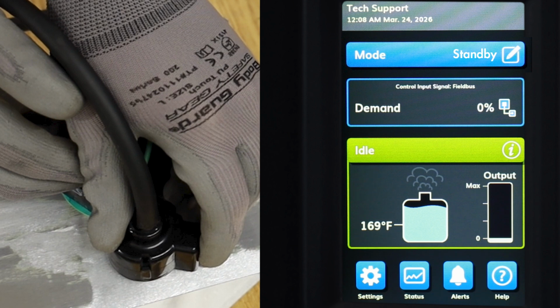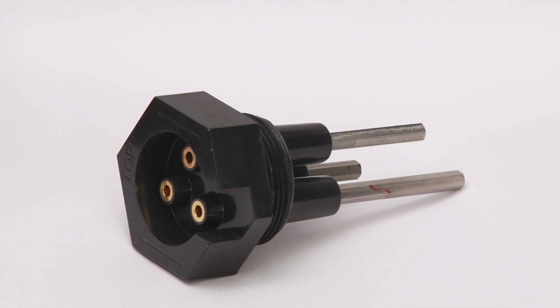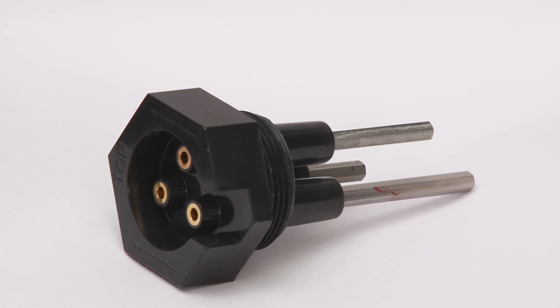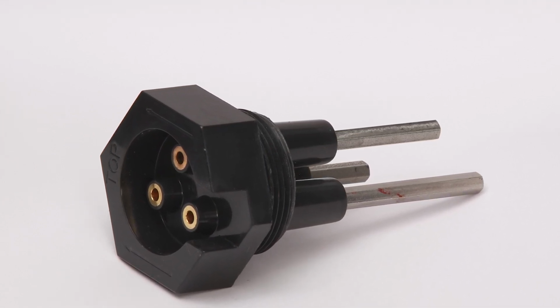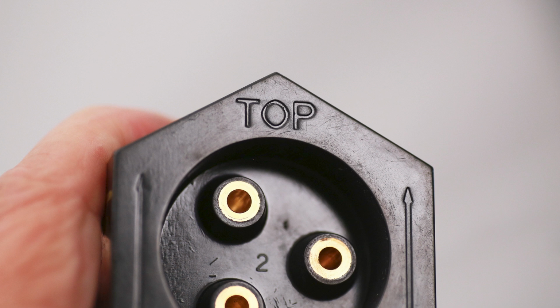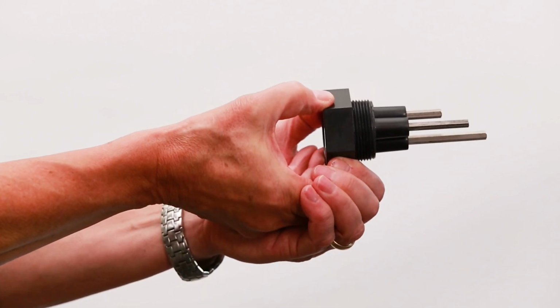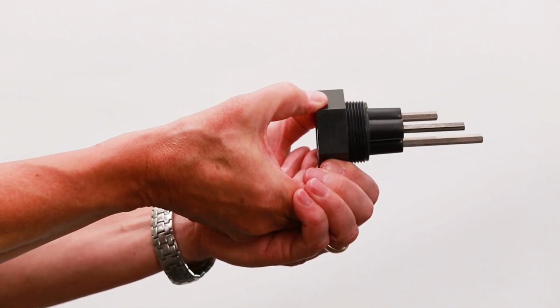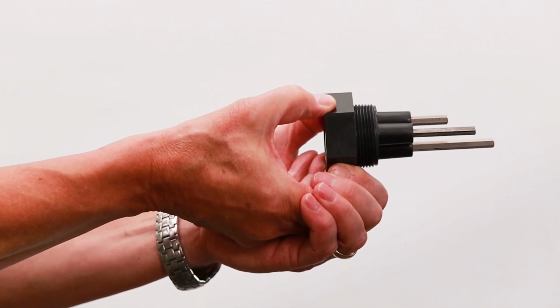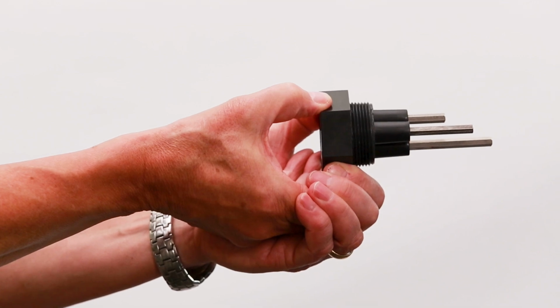It will show full. Another thing to check is that the rods are in the correct order on the probe body. Here's how you check. Orient the probe assembly so the word top is at the 12 o'clock position. Then rotate the assembly so you can see the side profile of the probes. The probes form stair steps, with the long probe as the bottom step.